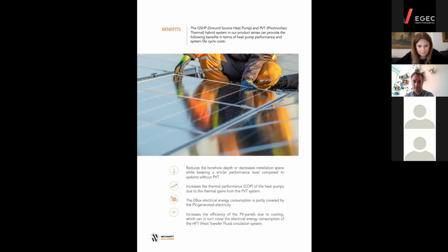The new hybrid e-box offers a complete carbon-free energy solution with numerous benefits. It reduces the need for borehole depth and decreases borehole space while keeping a similar high performance level. It adds increased COP due to thermal gains from the PVT. The e-box electricity consumption is partially or fully covered by the PV generated electricity, and it also increases the efficiency of the PV panels due to cooling of the heat transfer fluid circulation system.